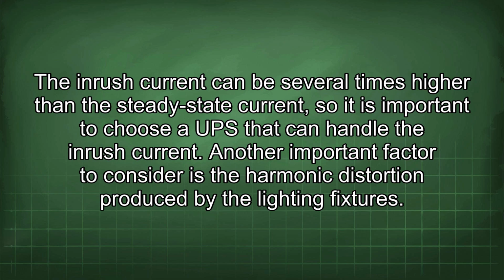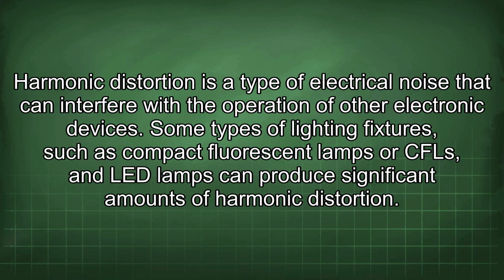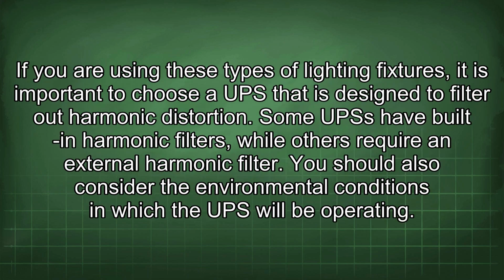Another important factor to consider is the harmonic distortion produced by the lighting fixtures. Harmonic distortion is a type of electrical noise that can interfere with the operation of other electronic devices. Some types of lighting fixtures, such as compact fluorescent lamps or CFL, and LED lamps can produce significant amounts of harmonic distortion. If you are using these types of lighting fixtures, it is important to choose a UPS that is designed to filter out harmonic distortion. Some UPS have built-in harmonic filters, while others require an external harmonic filter. You should also consider the environmental conditions in which the UPS will be operating.